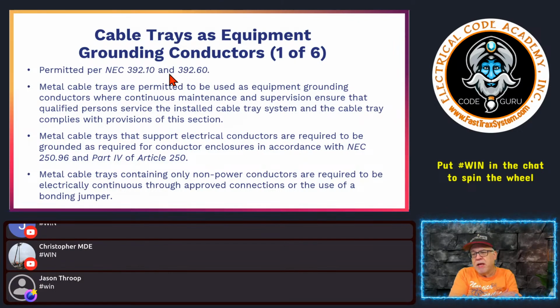Other than that, cable trays are designed to support cables. Also remember, as we talked about earlier, any SE cables or NM cables that you may install, because cable trays are not restricted just to industrial establishments. You can use them in residential, commercial, and industrial. But certain cable assemblies that go in there have to be rated and evaluated for use in a cable tray. That's what CT use means. It means it's been evaluated for use in a cable tray, through some testing, flame testing, and other things like that.